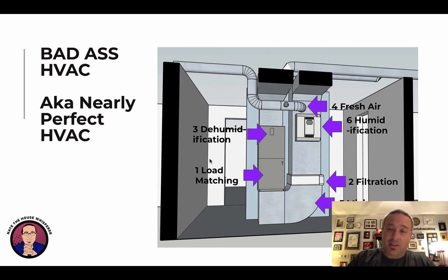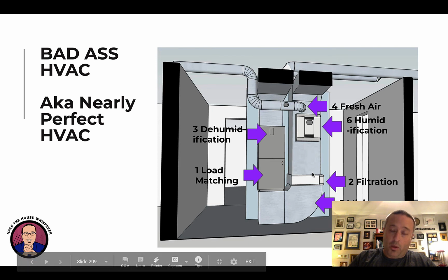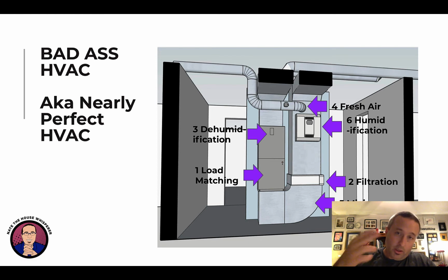So this tackles the 6 functions of HVAC, which is load matching - you want to have variable speed, throttle for it. You want to have filtration, which is the nice media filter. You want to have dehumidification, which can be done with reheat dehumidification with that resistance backup I was talking about last time. A fresh air line, so this is a fresh air duct that goes outside with a damper on it that closes when it gets too hot or cold. Mixing - you want to stir the house all the time and run that air through that filter, particularly as we are in the pandemic. One of the best things you can do is filter the air in your house frequently. That's true all the time. If you want to get sick less, filter your air a lot and have a really good filter so it actually knocks the garbage out. And then the last one is humidification, which isn't appropriate for all markets or all houses, but it can be nice to not have super dry skin.